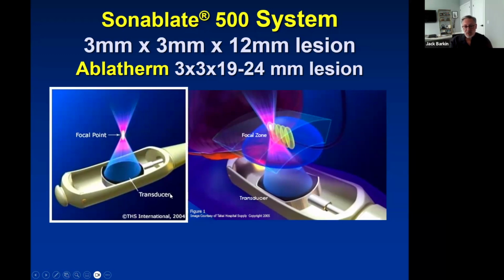And how did we treat? Using this transducer up the backside. And this is the first difference between the Sonablate, the machine that I'm using, that each time one of these little artifacts is created, basically it's 3 seconds on, another 3-second burst of energy, then a 3-second cooling cycle. So 9 seconds in total per segment. I treat an area 3 millimeters by 3 by 12 millimeters high, which is important. Whereas on the Ablatherm, the French machine, they're treating 3 by 3 by 19 to 24 millimeters high. So very significant difference. And why is that important?